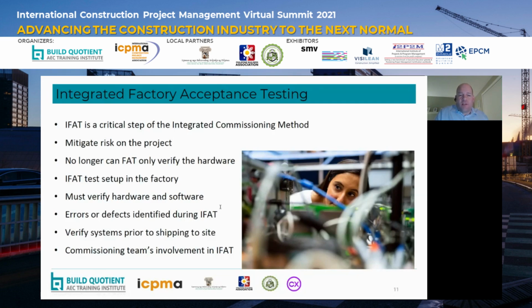What that means is that the hardware and the software are only meeting for the first time on site during commissioning. And essentially what you're doing at that point is still debugging the software. Having an integrated factory acceptance testing where both the hardware and the software are verified in the factory before it leaves to go to site verifies the hardware is correct, but also verifies that the software design is correct.